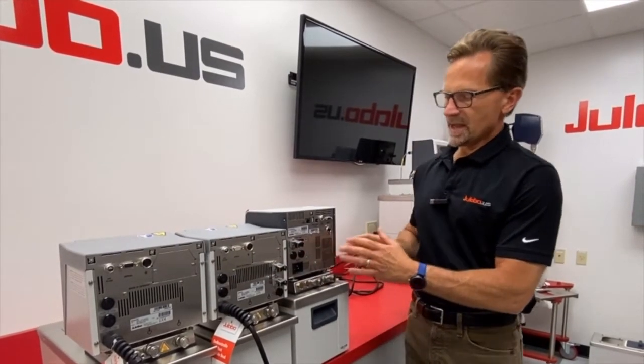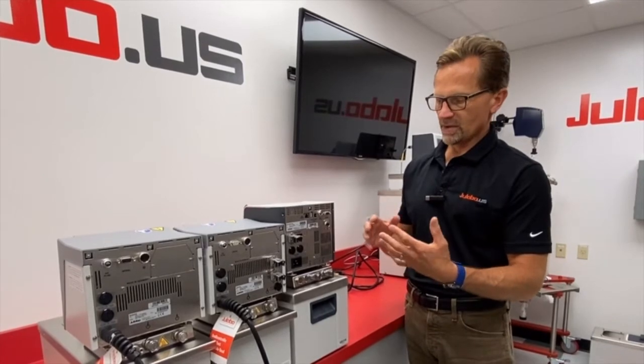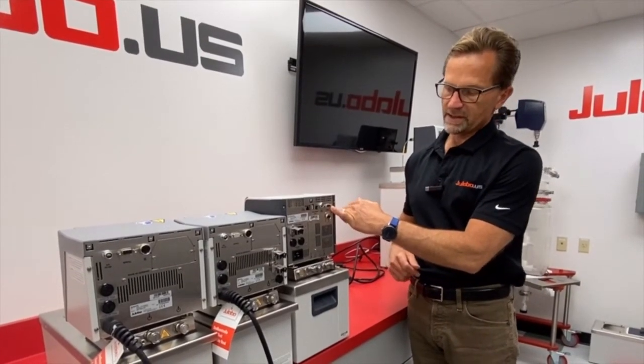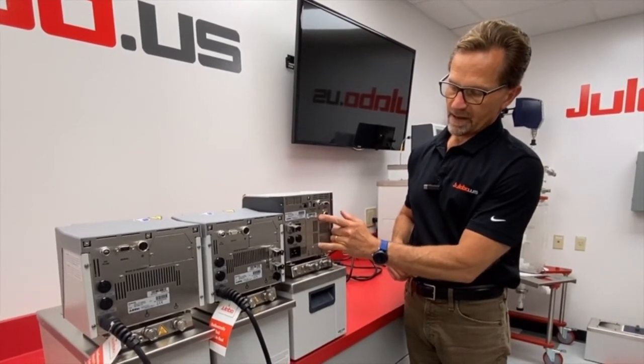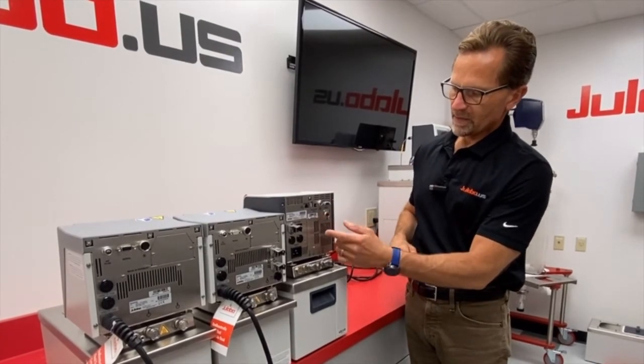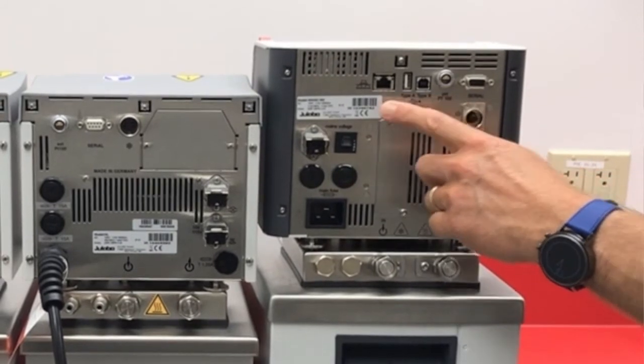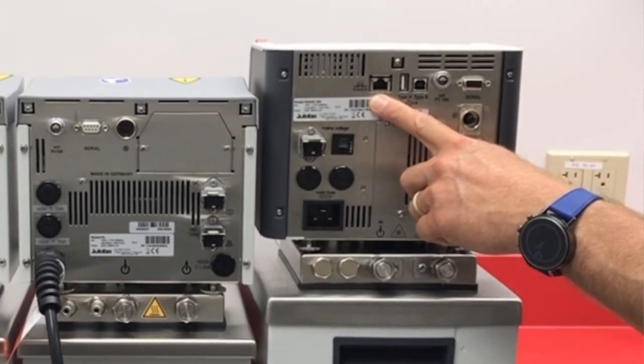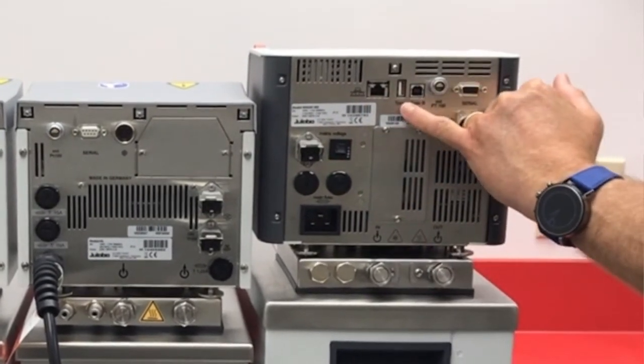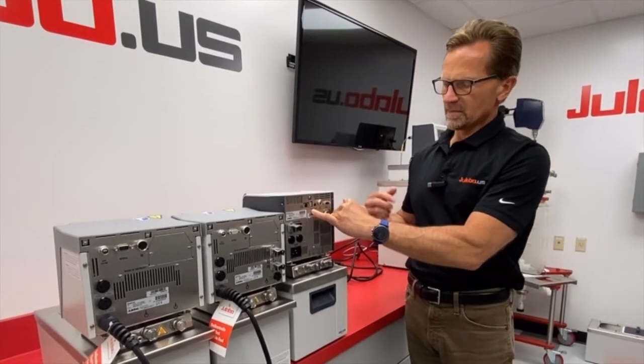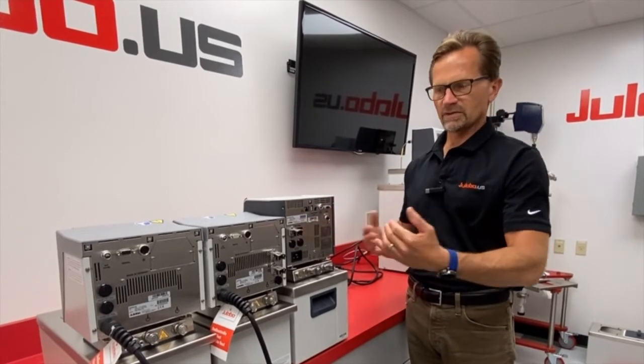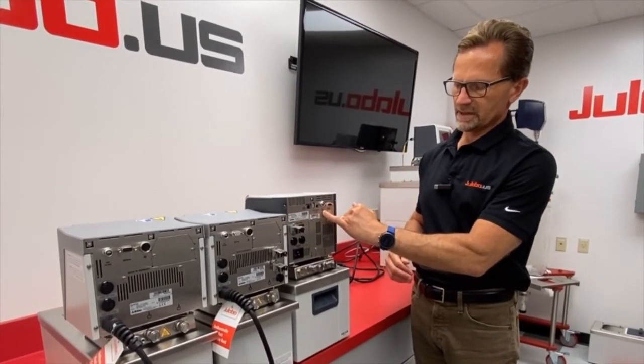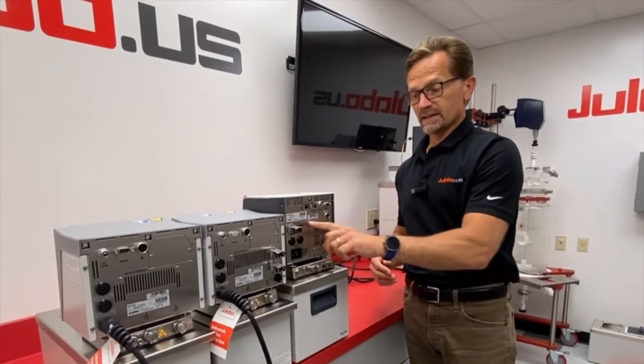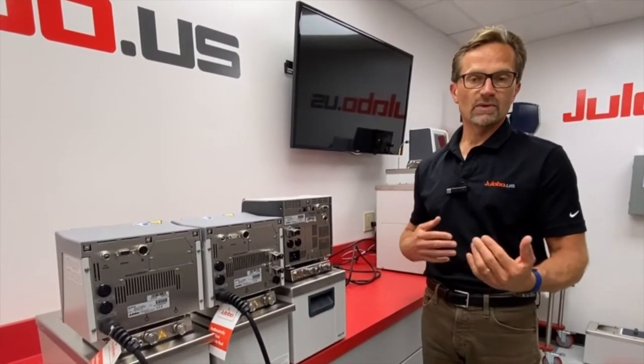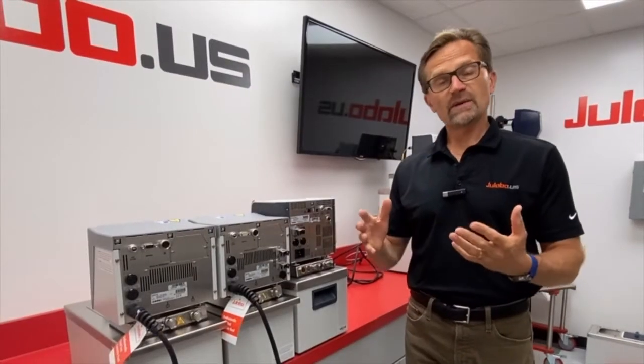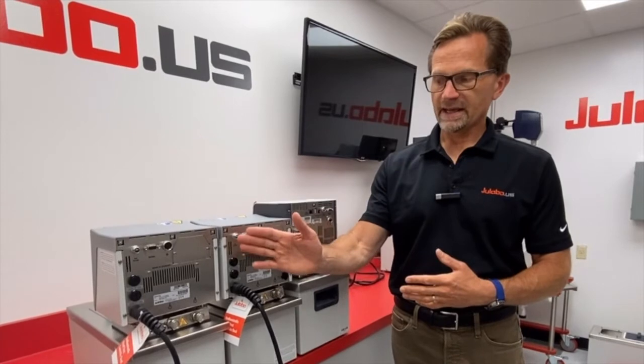If we step over to the MAGIO MS system, you'll see that it has a lot more I/O options. We have the serial port here, which incorporates RS-232 and RS-485. You have an optional slot here for analog, for current or voltage. But we also have a USB Type B for communication to a PC and Ethernet. So this also can utilize Modbus TCP/IP protocol. A USB Type A port for data logging, profile saving, program saving, and the like. You can transfer those between different MAGIO units. And the external PT100 sensor port. The MAGIO has just one solid state relay (SSR), again, for use with solenoid valves for cooling water or the inline flow circuit.